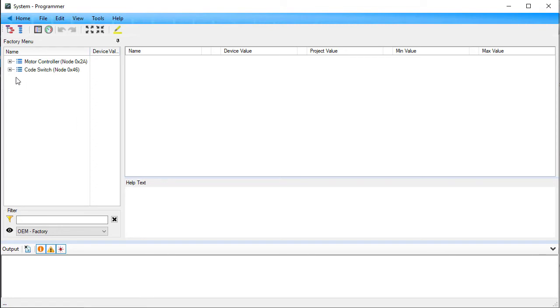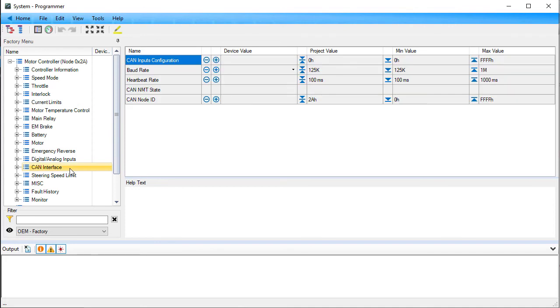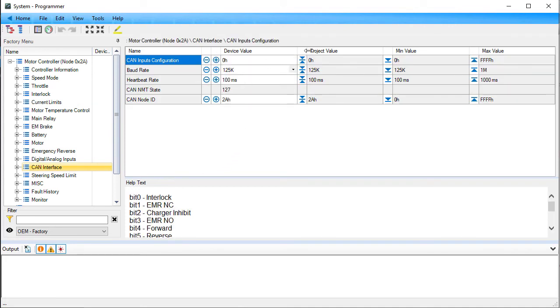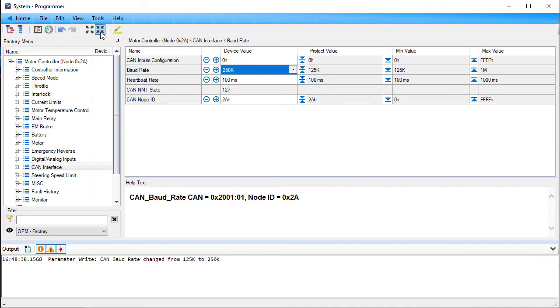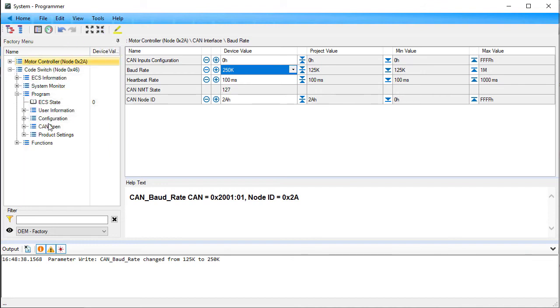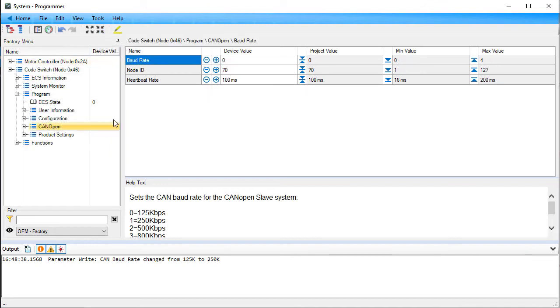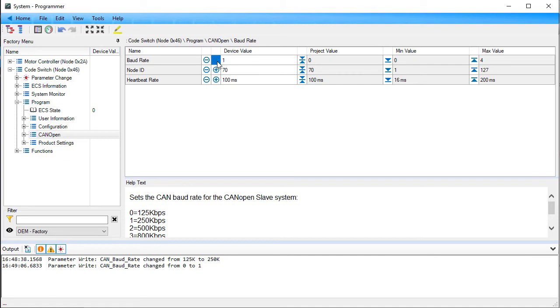Find the parameter that specifies the first device's baud rate. Change that to 250K. Now we'll find the second device's baud rate parameter. I'll change the value to 1, which is how the device's baud rate parameter indicates a 250K baud rate.